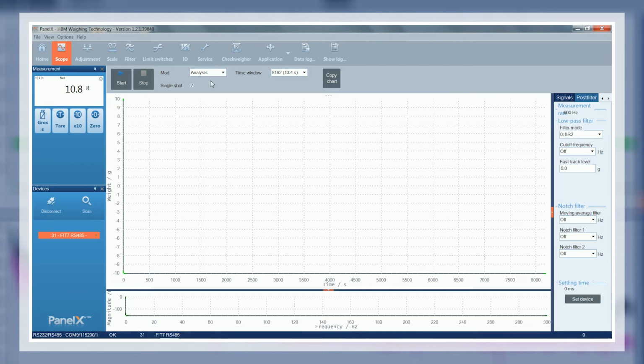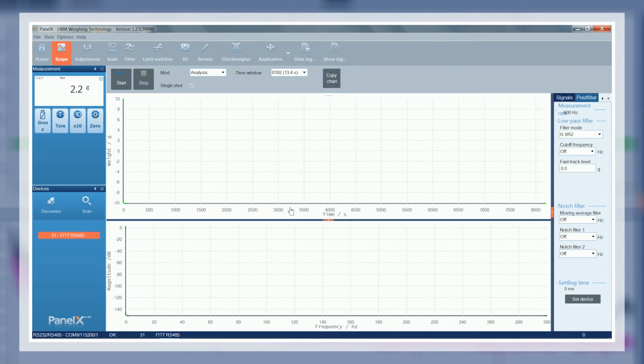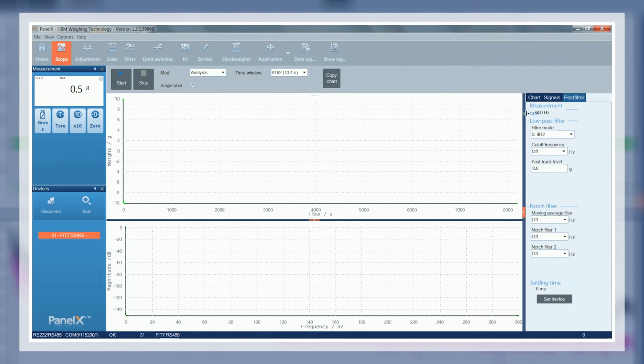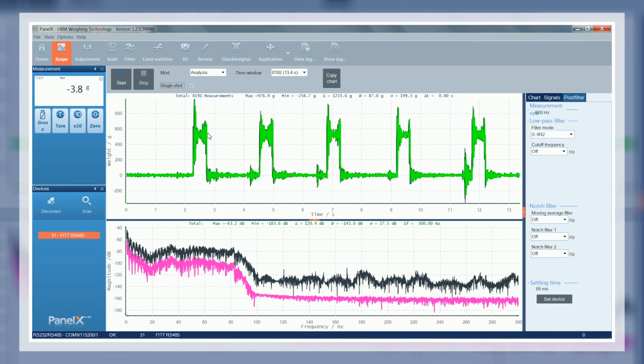Then we will increase the number of data points for analysis. The number of data points defines the length of time available for doing the test measurements using the test weight. We allow the test weight to pass over the load conveyor several times. When the weighing procedure is complete, the system will display the timeline of the raw signal in the scope view. Typically, the raw signal will contain a lot of noise and numerous interferences. The overshoot of the mechanical spring element of the FIT-7A can be seen clearly as soon as the test weight is on the load conveyor.